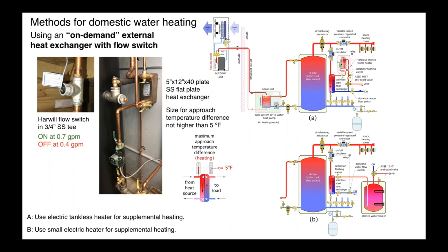The other side has the cold water coming in, and it goes in counterflow, and it gets a preheat effect through there. And what turns the circulator on is this little flow switch. We actually wired that flow switch, which detects anytime domestic hot water demand gets up to or above 0.7 gallons per minute. And it's a little reed switch.